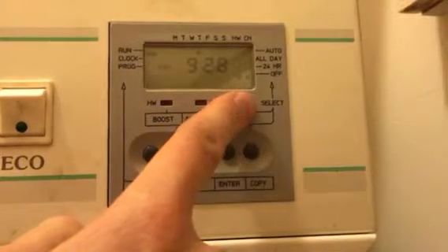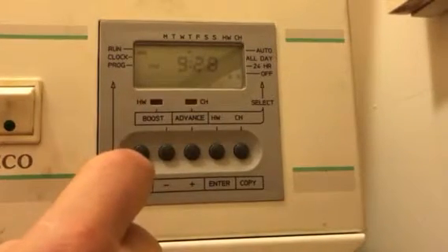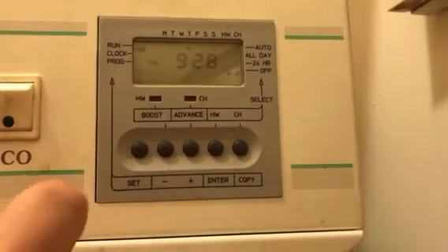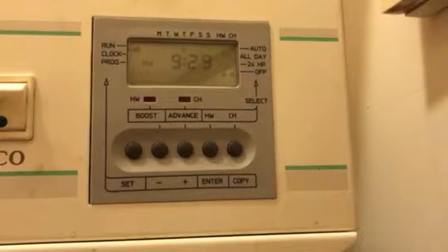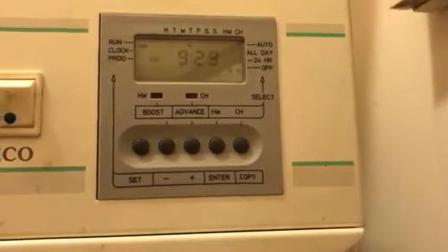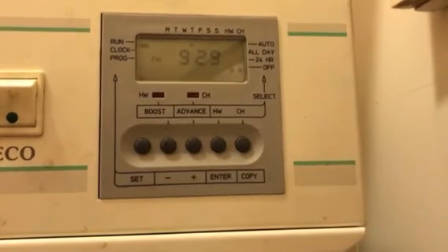You may notice the bottom 2 icons on the right here show that both the hot water and the central heating are currently off, so they're not using the timer at all. But if I moved them to auto, then they would use all of those modes. If I moved it to all day, they would switch on at the first one and off at the last one. If I set them to 24-hour, it would ignore the clock and it would always be switched on. There are of course various thermostats and safety valves and things that also need to be enabled in the proper way before the boiler will actually fire and heat up.